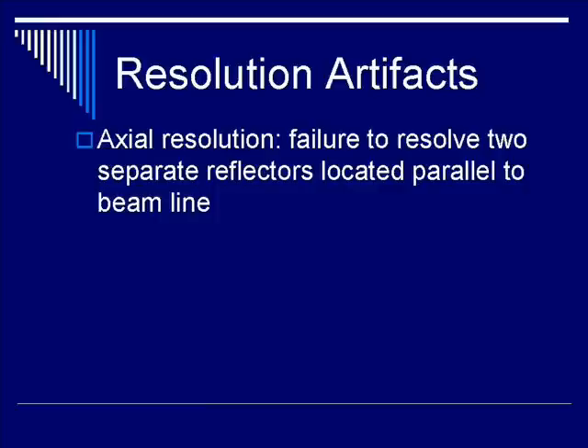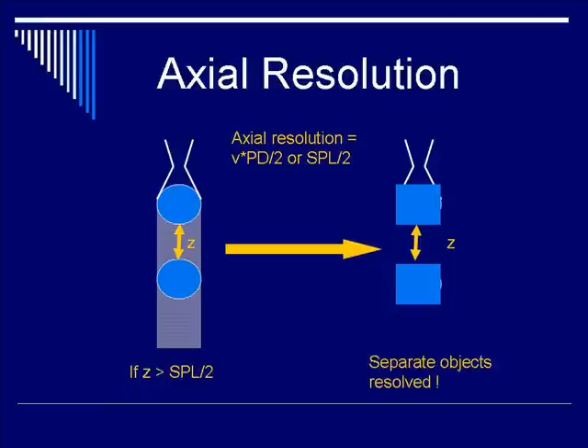Let's start by talking about axial resolution. By definition, axial resolution is defined as the failure to resolve two separate reflectors located parallel to the beam line. Taking two point reflectors separated by spacing Z, recall that axial resolution equals the velocity of sound times pulse duration divided by 2, or simply the spatial pulse length divided by 2. If the separation Z is greater than SPL/2, you can resolve the two objects — two pixels will show up on the ultrasound screen separated by spacing Z.